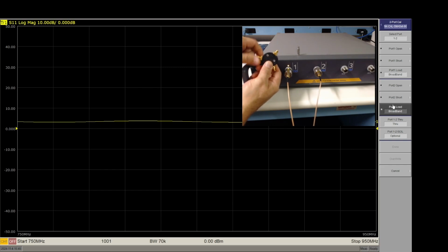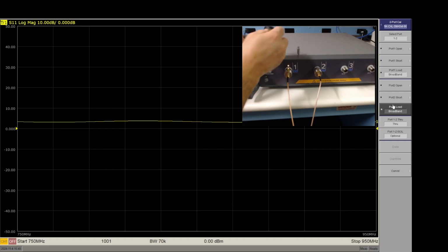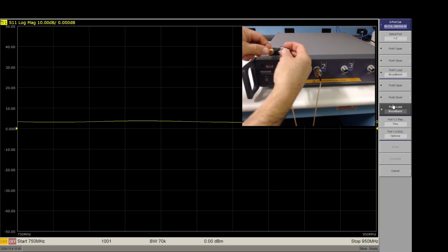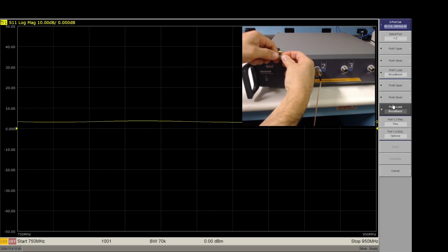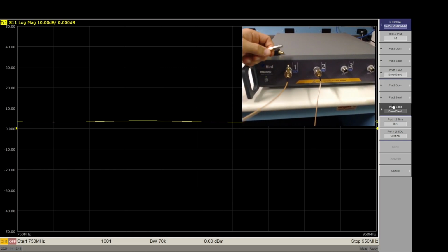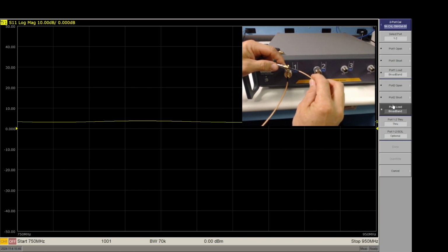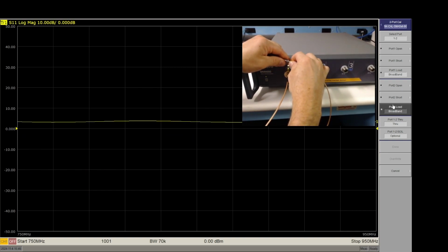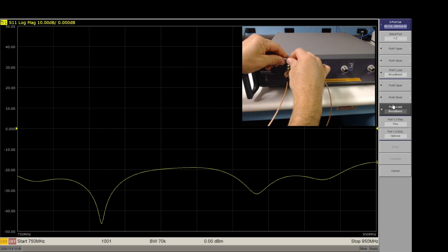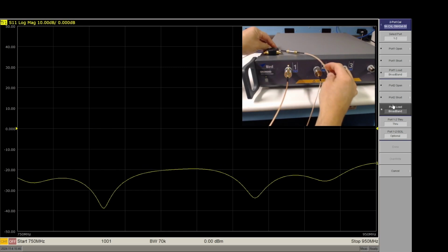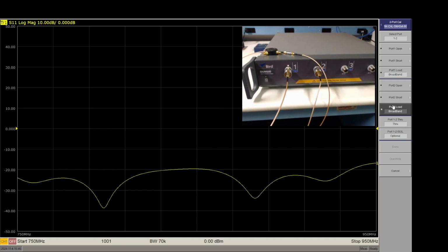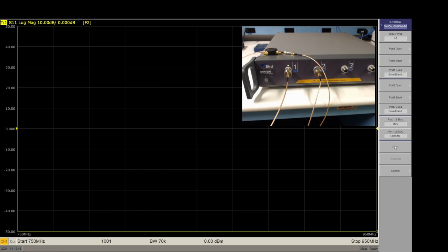Connect the ends of the cables from both ports 1 and 2 to either side of the through device. Click on the port 1-2 through button. Finally, click the Done button. The measurement trace may drop out of sight. Moving down to measure the noise floor with the load device still connected.